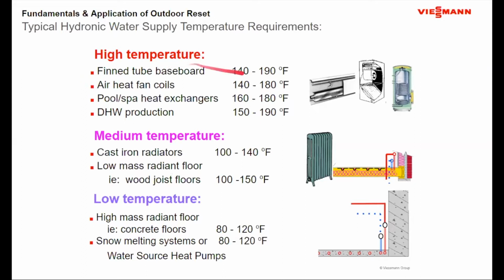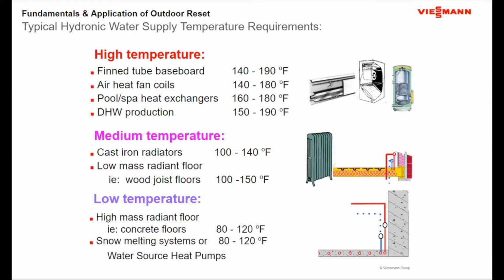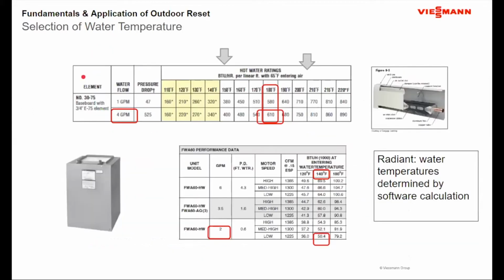So from a design standpoint, when I look at this design water temperature based on the methodology that I am using to heat that building, a lot of times that locks me into a bracket of potential temperatures for the water for my heat emitters. So if I choose my heat emitters, and I'm going to go looking at, for this, really the high temperature ones, this happens to be performance numbers for a baseboard. It's a Slant/Fin baseboard. Down here are performance numbers for an air handler. It happens to be a First Company air handler.